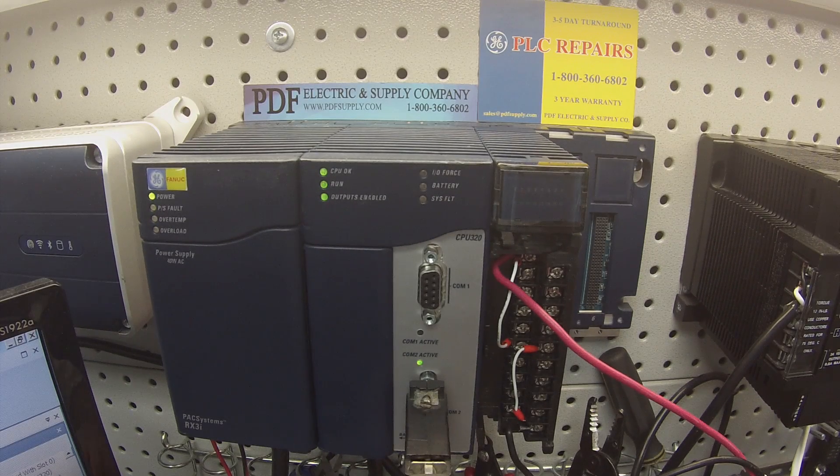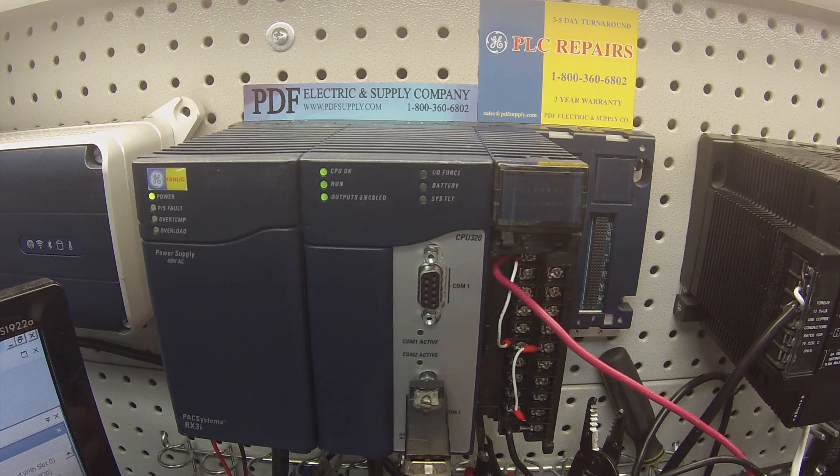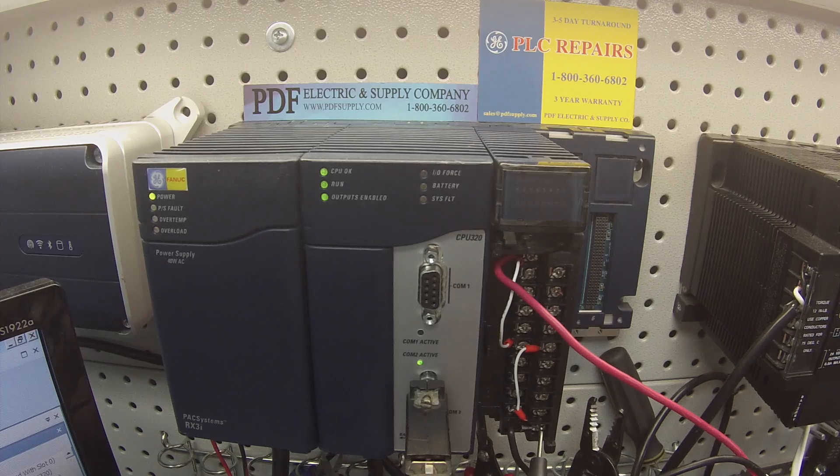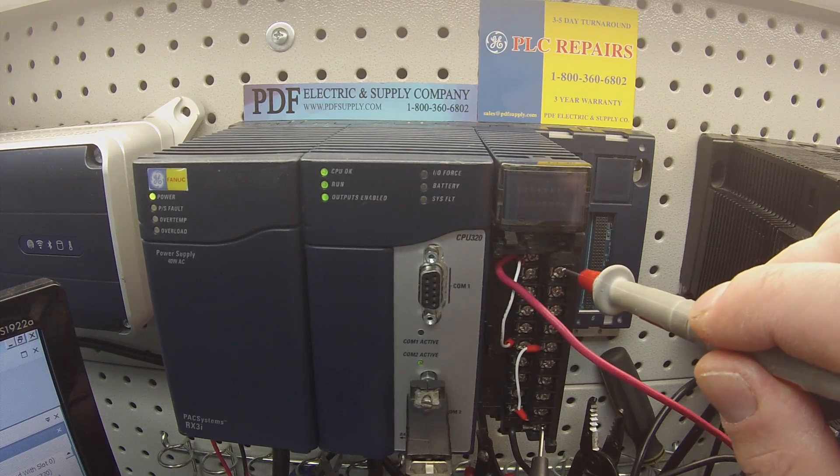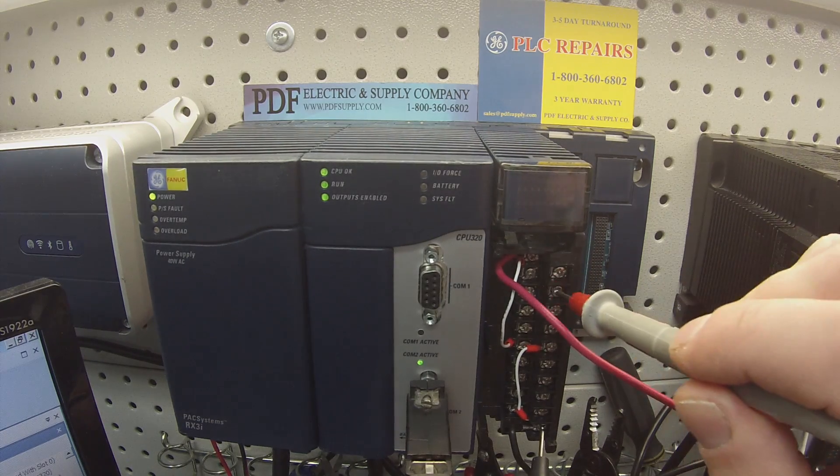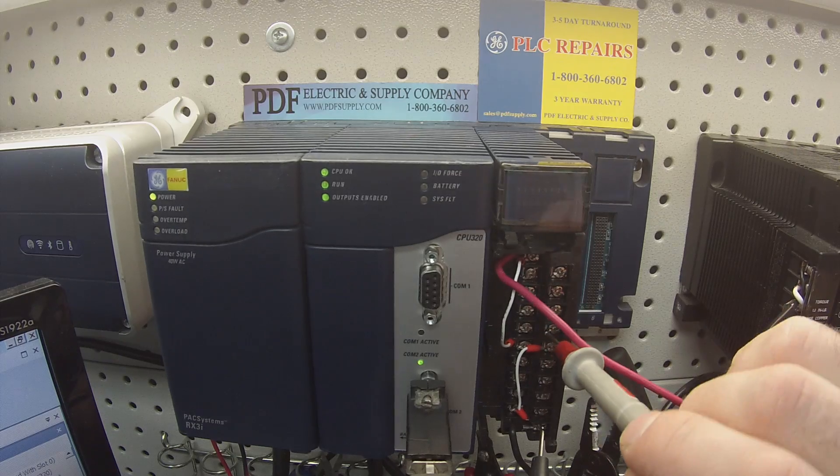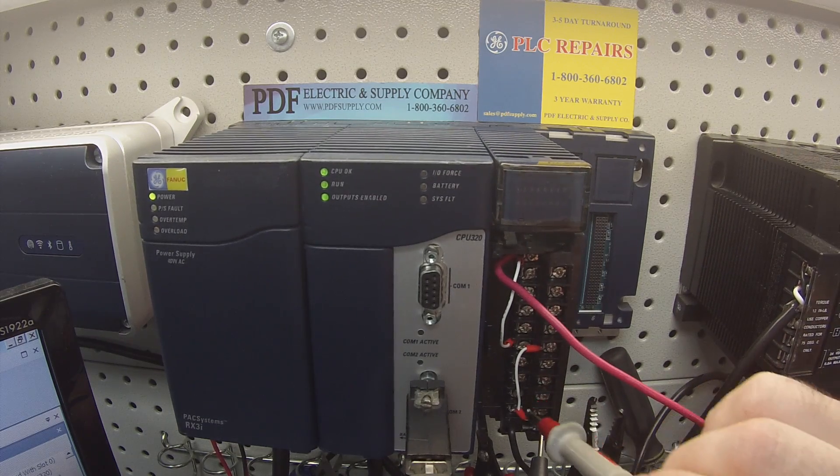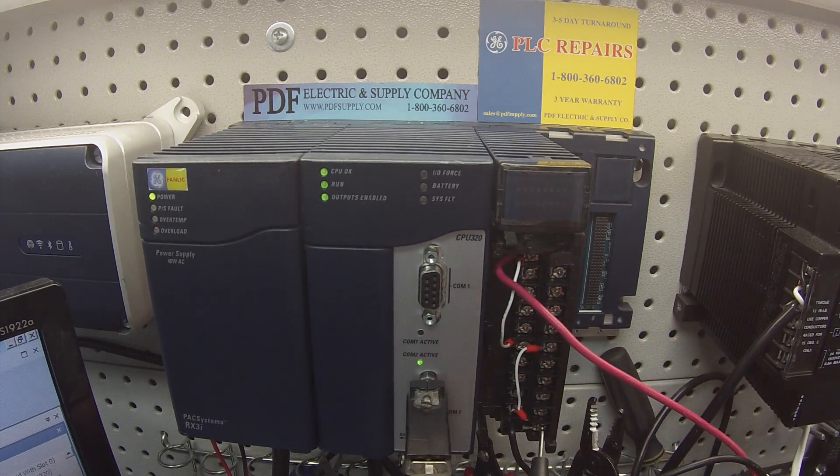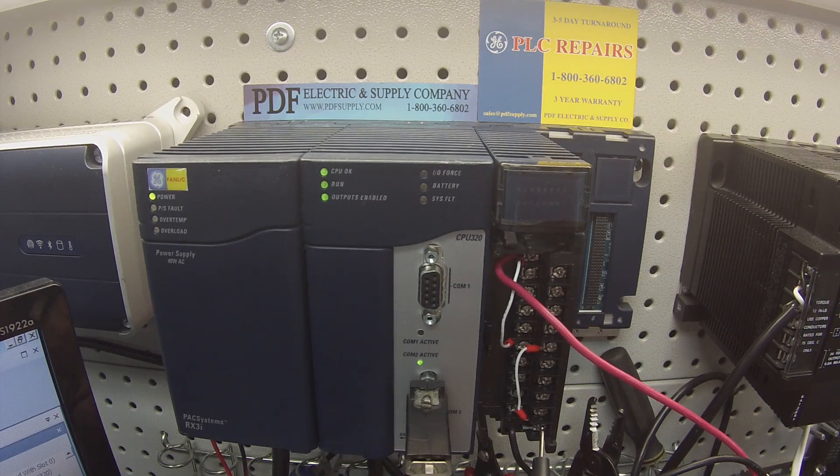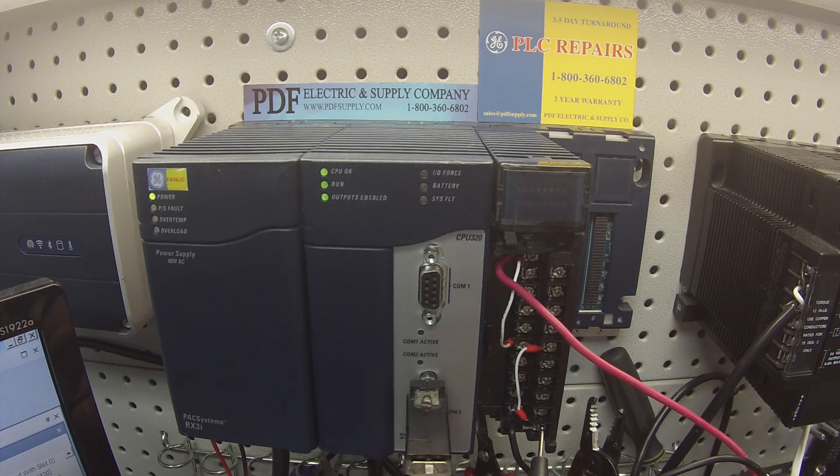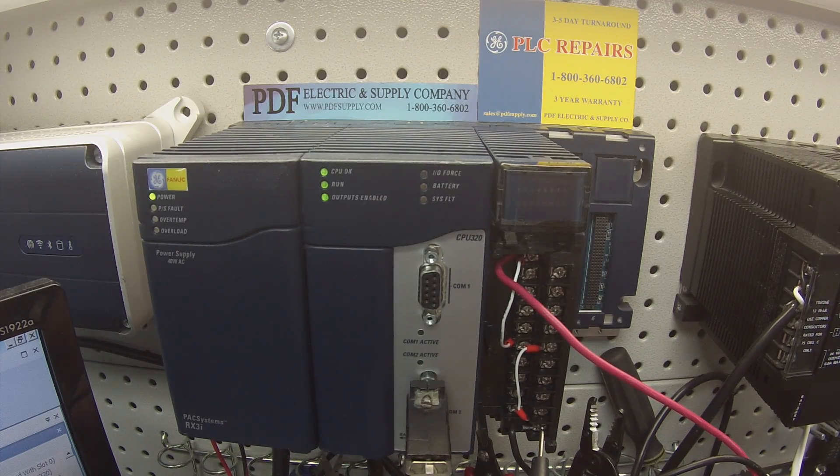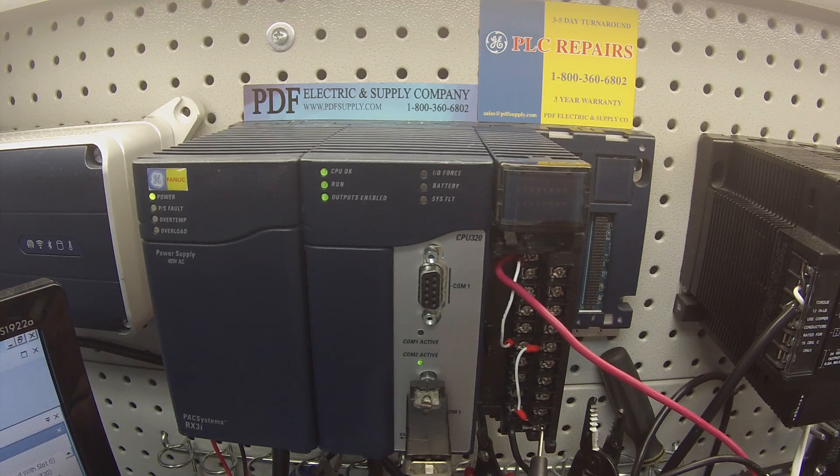The other way to check is that when they're all in the off position, they should still remain off. I'm going to go ahead and probe all my channels even though they're off. Occasionally you'll get one that turns on. That means that it's failed in the closed position. You don't want that. That's a problem.